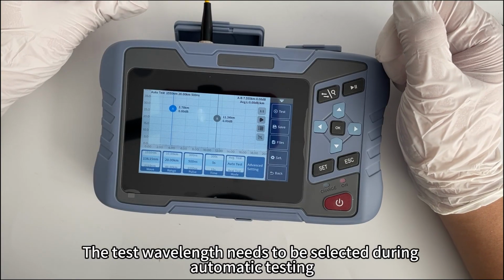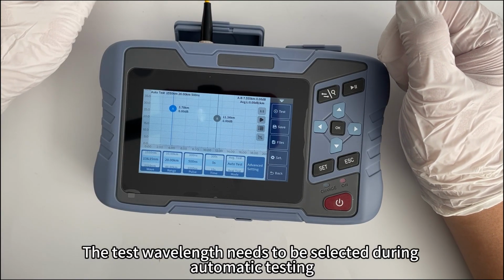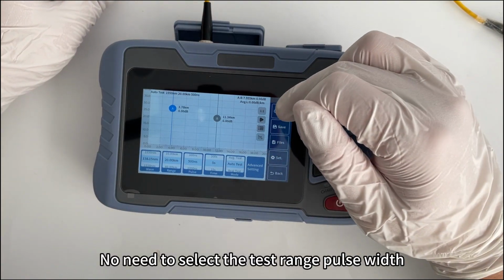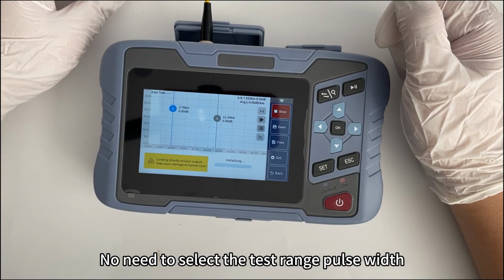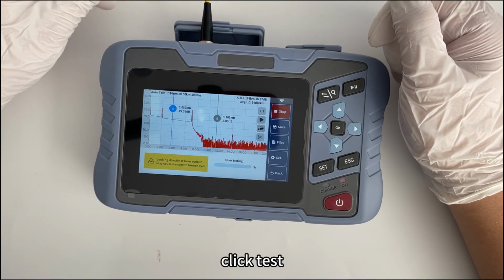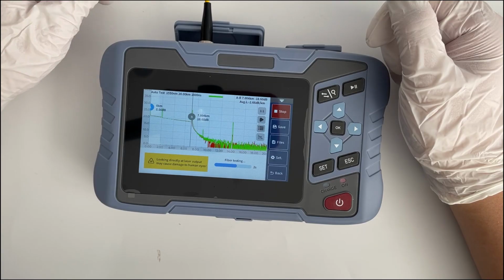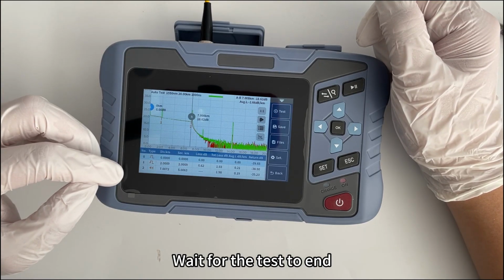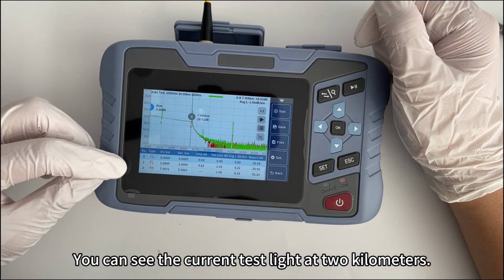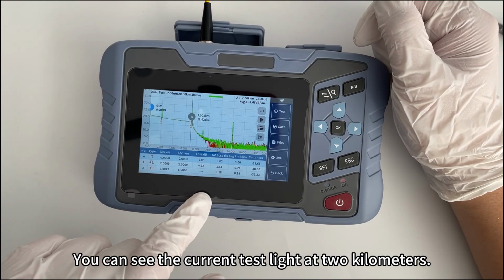The test wavelength needs to be selected during automatic testing. No need to select the test range or pulse width. Click Test. Waiting for the test to end. You can see the current test light at 2 kilometers.